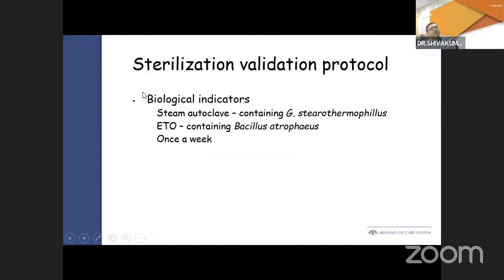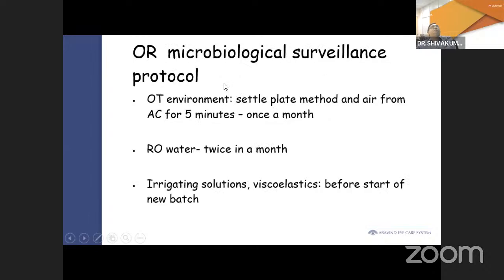Also for the functioning, we have the biological indicators. For the steam autoclave, we have the Geobacillus stearothermophilus and Bacillus atrophaeus, and this is done once a week. The OT microbiological surveillance may probably be dealt with later in another talk, but the OT environment should be checked once a month, RO water twice in a month, and irrigating solutions and viscoelastic before we start using the new batch.